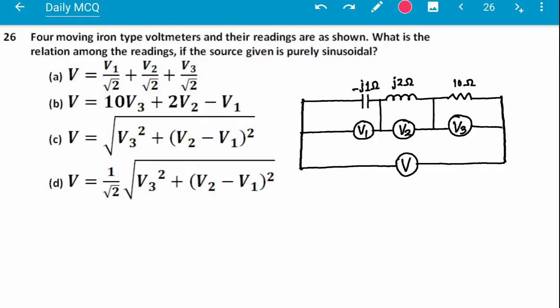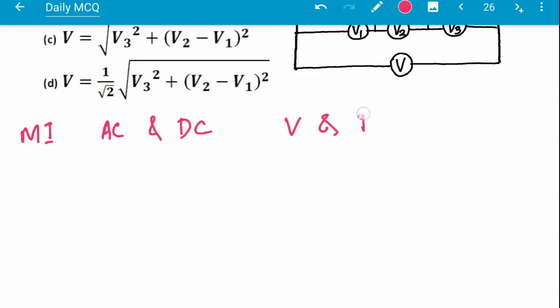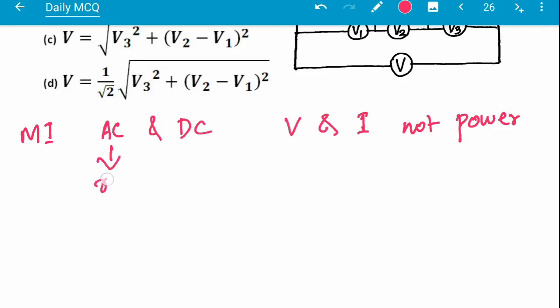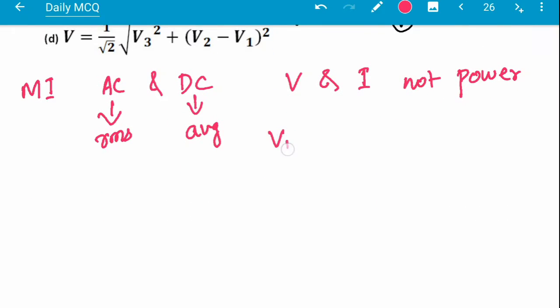Two things come first: measurement — what type of voltage does a moving iron type instrument measure? Average or RMS? The answer is that a moving iron type instrument can measure both AC and DC, but not power. For power, dynamometer type instruments are used. In AC it gives RMS value, and in DC it gives average value. So the readings V1, V2, V3, and V are all RMS values.